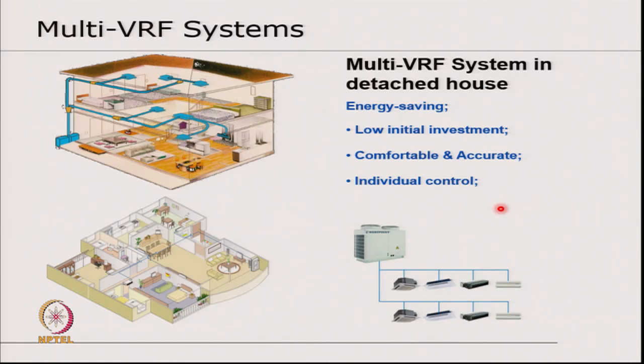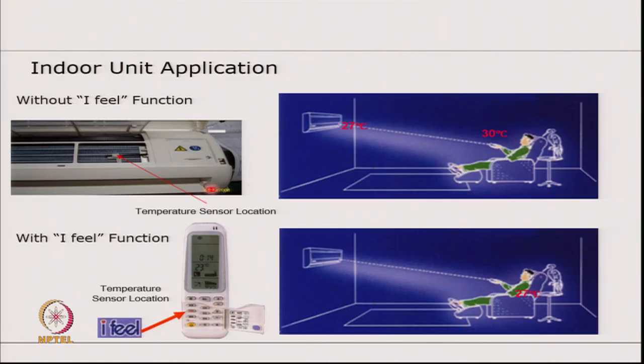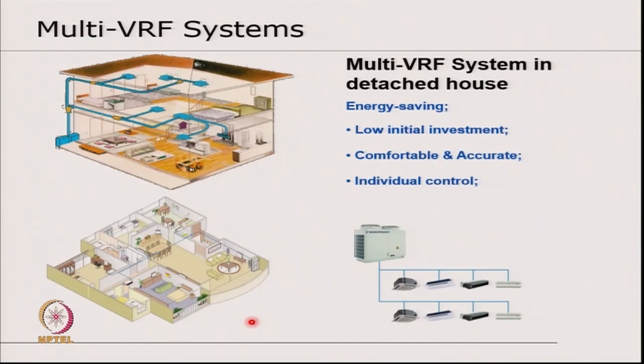Yeah, the key thing in the previous slide, sorry about that, was that the temperature sensor which is controlling the compressor on off is located in the return air path, very close to the evaporator coil over here. So when we are altering the set point, we are actually altering the temperature here, and the key difference in this feature is that you are making the air conditioner respond to temperature where you are. Again, that feature is not needed if the entire space is at a uniform temperature.